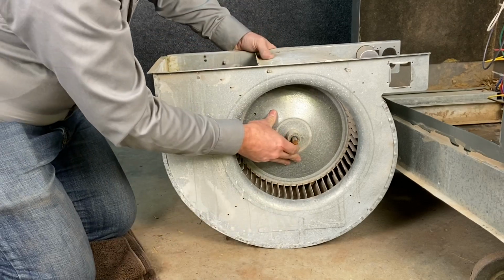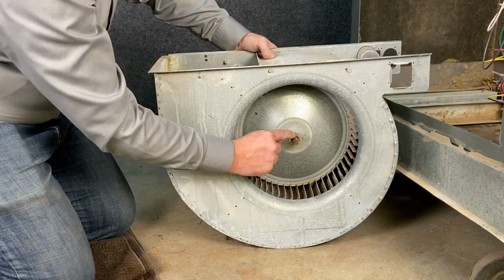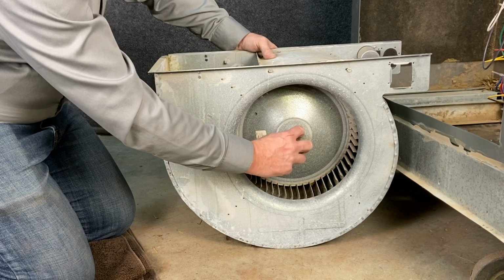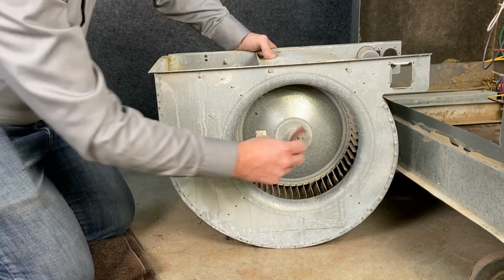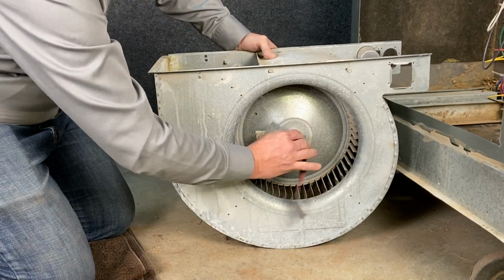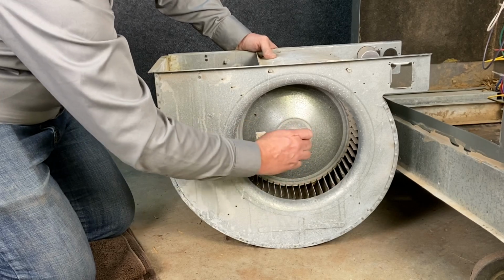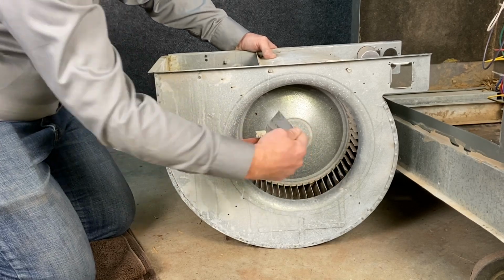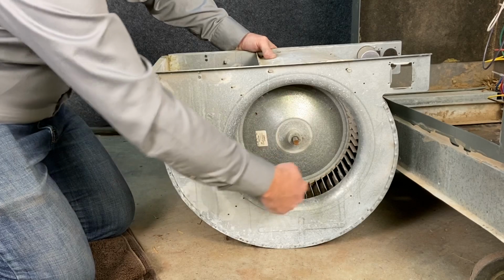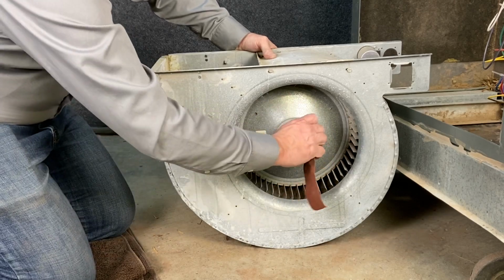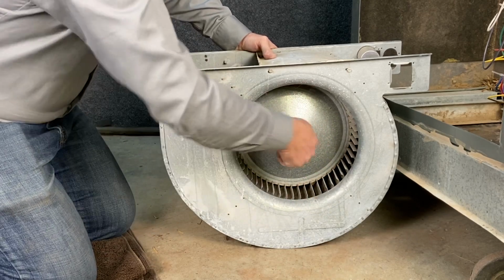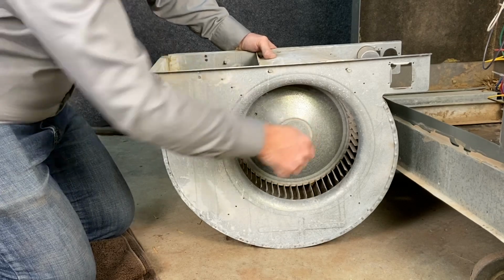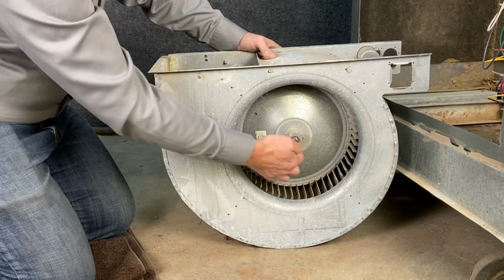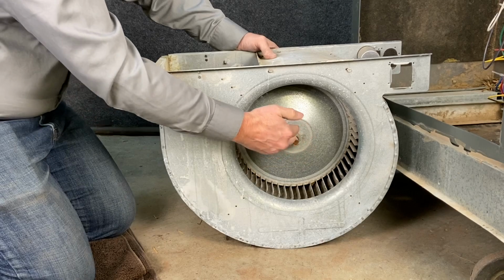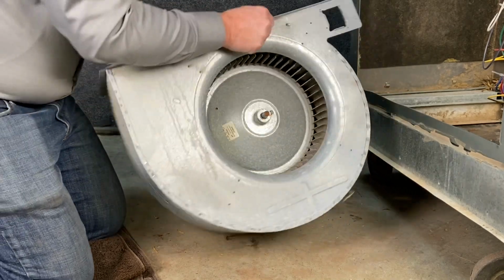Now one more thing I'm going to do is push this wheel inward, and now there's going to be a little bit of a groove right there where I couldn't get the sand cloth. So I'm going to sand that last little bit right there, and I'm not going to be able to spin this wheel now because this housing, this squirrel cage wheel, the blower wheel, is shoved up against the side of the housing. So I'm going to sand this down to make sure it's nice and clean, and I'm going to turn it on its end and put a little bit of oil through here so that the oil will go through there to make that easier to come apart.